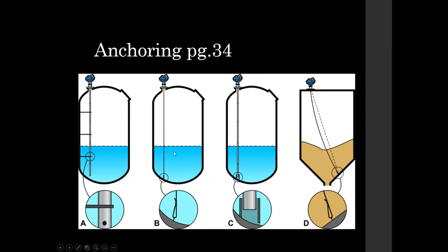Anchoring, again, we've touched on this many times, whether it's bracketed, unistrut, U-bolts, or whether it's an eye and it's tied off, or whether it's a sleeve, it doesn't really matter as long as it's fixed to the vessel some way. Particular note here in diagram D, dealing with solids, and this angle of repose, you want to be perpendicular to that surface if you can, plus or minus 5 degrees.